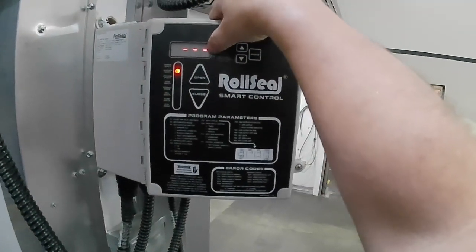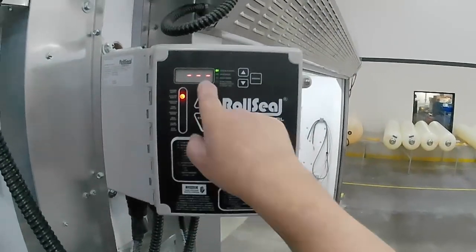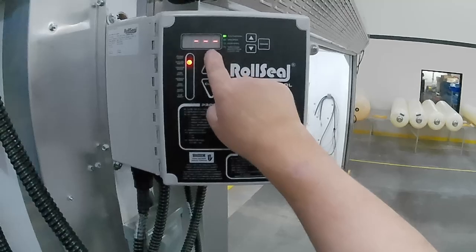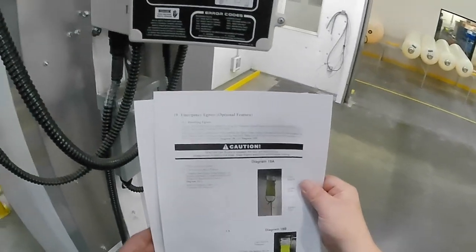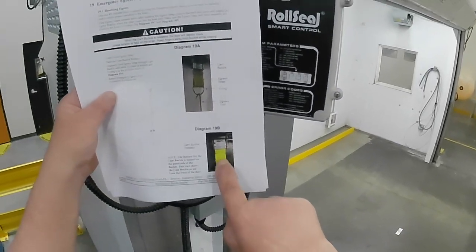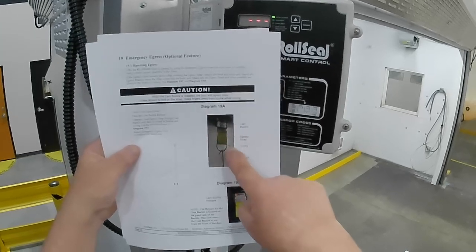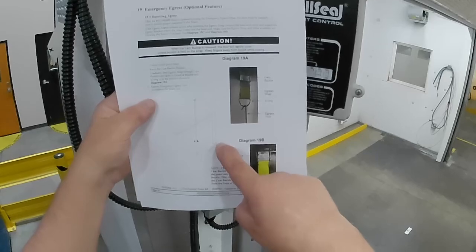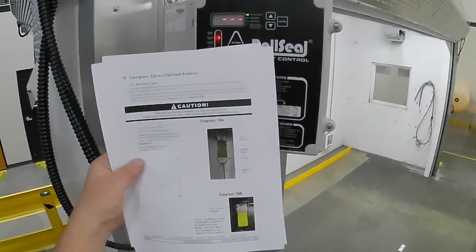The other thing that I looked at was when the door is fully down, these three lights, these three flat dashes indicate that the encoder doesn't know its position. So I was looking into that also, and while I was in the manual reading, I also came across this little strap that you guys may or may not have seen on the inside of the operation. This is a manual pull-down, which is an automatic egress. If you pull this strap down, it will pull up that curtain so nobody gets stuck in there, right?